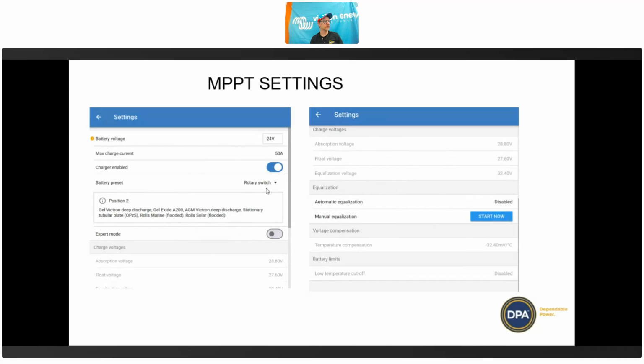The ones that I recommend people use most of the time, I don't usually recommend people use the presets that they have, unless you have some sort of unknown battery. I think you normally want to set it according to the battery manufacturer's instructions. But what I would recommend is you go into the battery presets and select a preset which is of the same type of battery that you have, and then go and edit those.